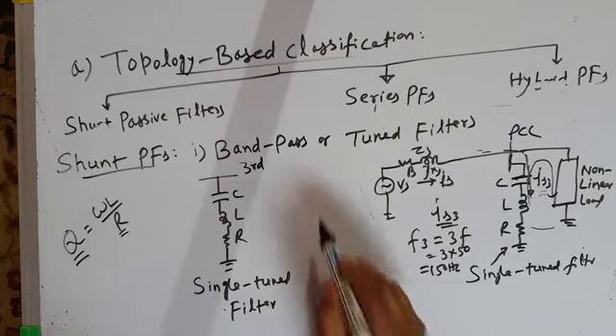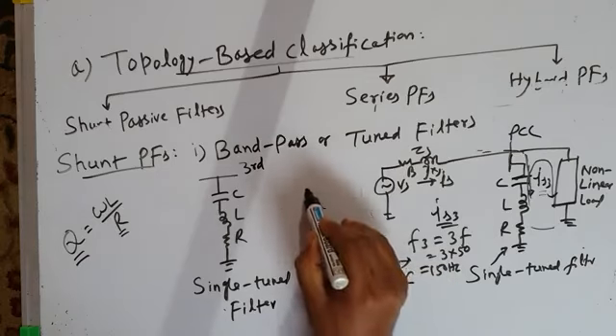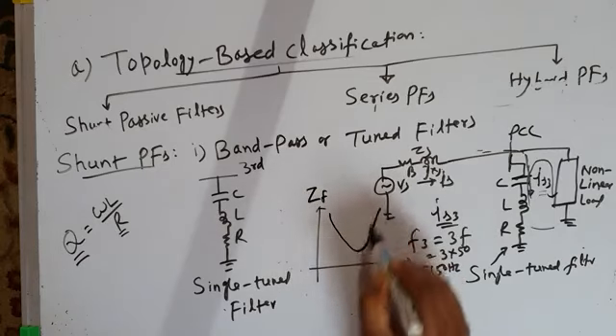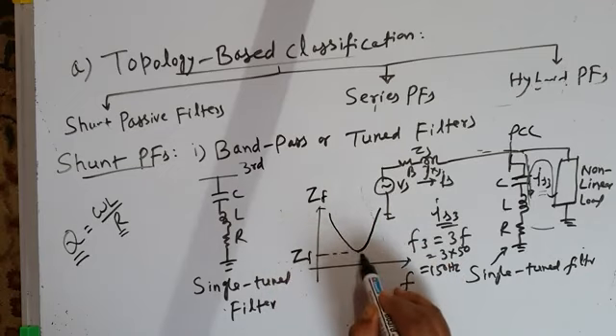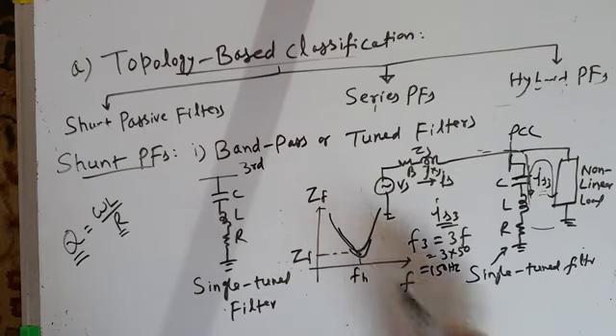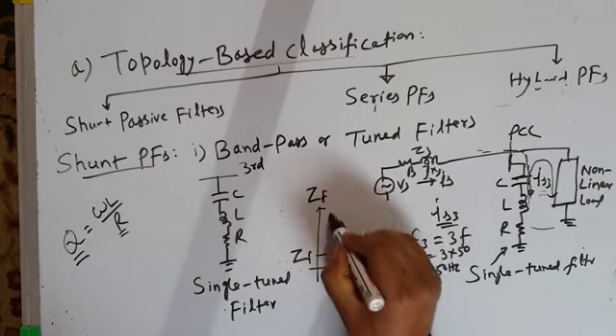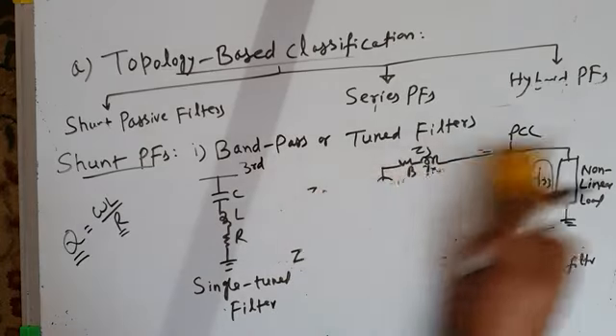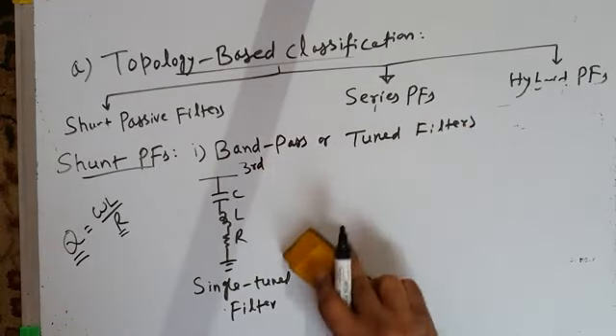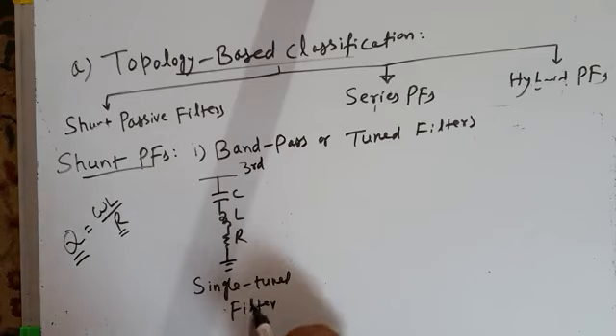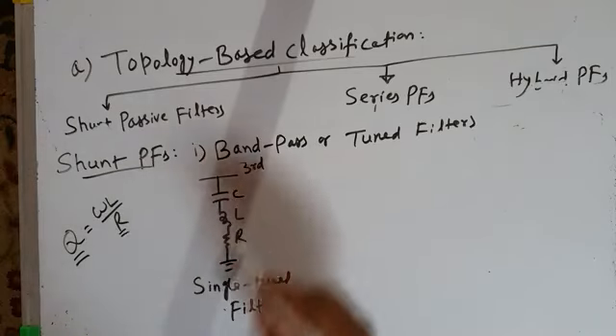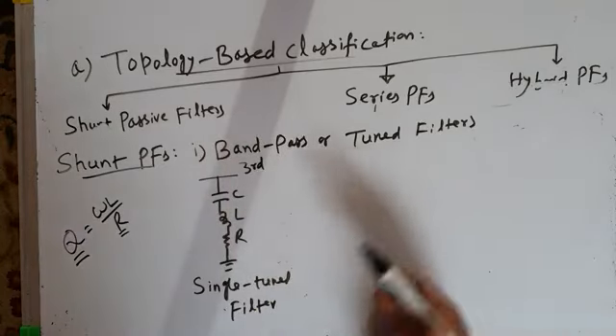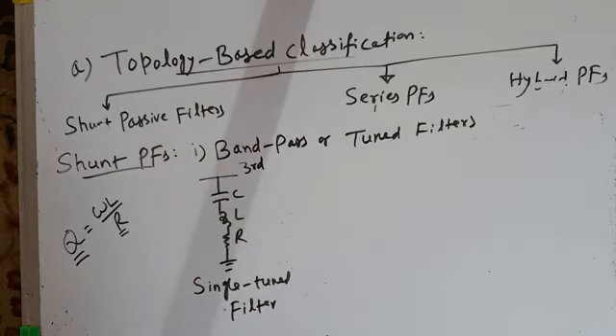So the source current is free of third harmonic current. In terms of impedance vs frequency, the filter presents very low impedance at the particular harmonic frequency it is tuned to. This is how a single-tuned filter traps a particular harmonic component of current. It is called 'single-tuned' because it is tuned to a single harmonic frequency — say third, fifth, or seventh, depending on which harmonic you want to suppress.